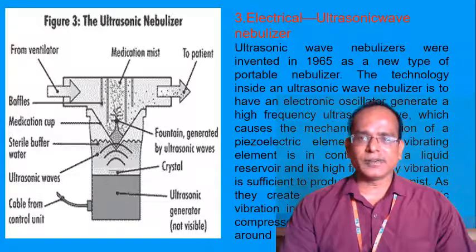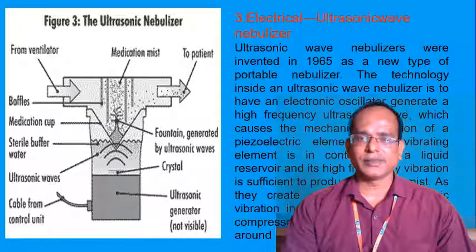So this is operated, that means ultrasonic waves are created with the help of an electrical signal. So they are using a piezoelectric crystal, in which they apply electricity. With the help of electricity it will convert an electrical signal into ultrasound. That sound reaches the bottom of the chamber. So there are water droplets created, which reach the upper chamber. They are pushed by the baffles. It directs moisture or molecules moving towards the patient.